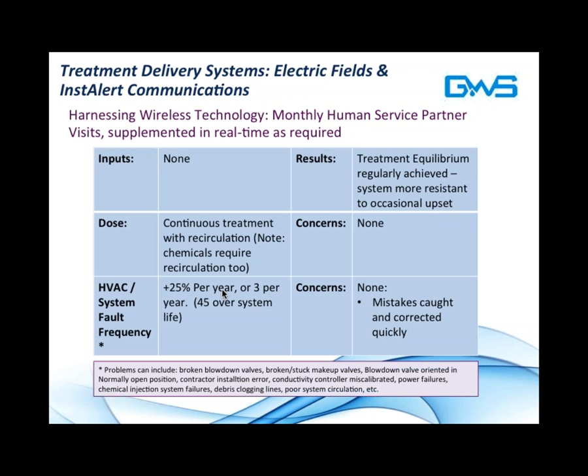So with a package system now, what happens? We have zero inputs, electricity aside. Of course, that's required in chemical feed stations as well. The result is that you have treatment equilibrium regularly achieved. The system is much more resistant to occasional downstream system upsets. Dosage, there's continuous treatment as long as there's recirculation. So there are no chemicals required in the process, which means that blowdown can be reused on site.